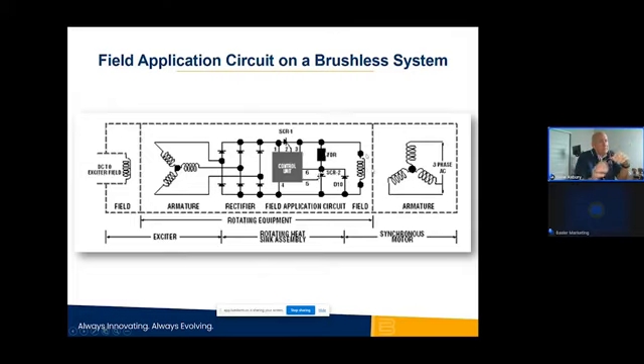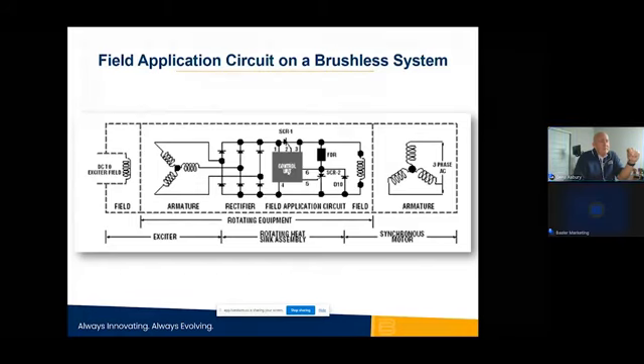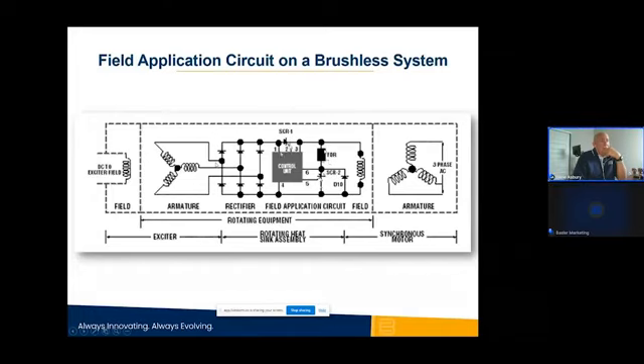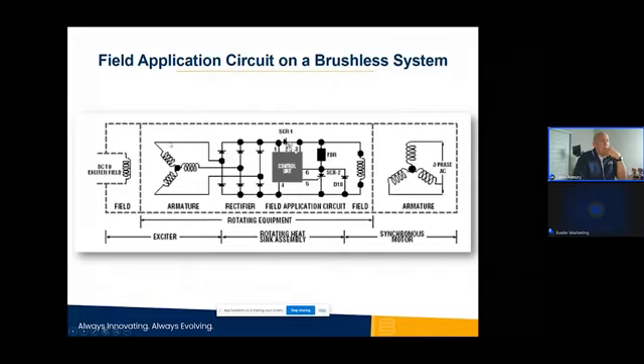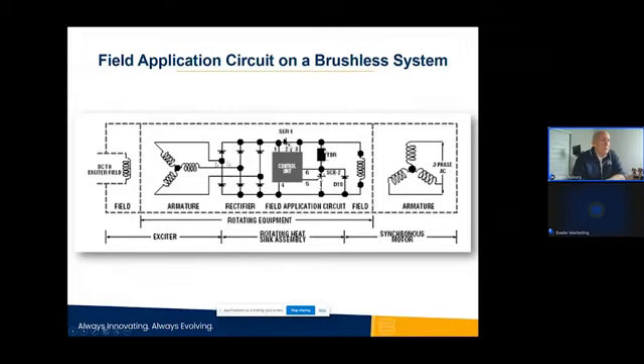So as that starts collapsing to zero, the control unit would monitor that, and at about 97% speed, it will gate SCR2 that's in series with the field discharge resistor off, and it will gate SCR1 on. And so, taking the FDR out of the circuit and supplying excitation through the AC alternator or armature being rectified through the rotating exciter or diodes on the brushless exciters, and applying field to the main field of the motor.